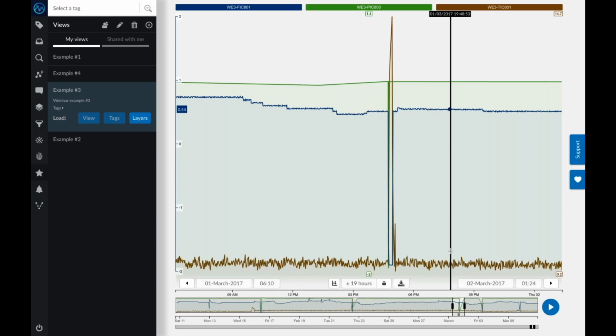But what was found was that, by overlaying some layers, by using the influence factors, which I will not explain today, but which is basically an automatic search in the background for correlations, for trying to find out what is influencing the behavior I have on my screen, what is influencing those trends, we found out that there was a very short but severe spike in the steam network itself. So there was a very short spike on the pressure in the steam header, and right after there would be a problem with my steam measurement itself.